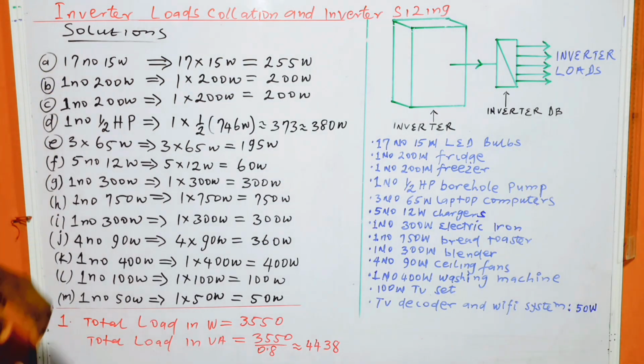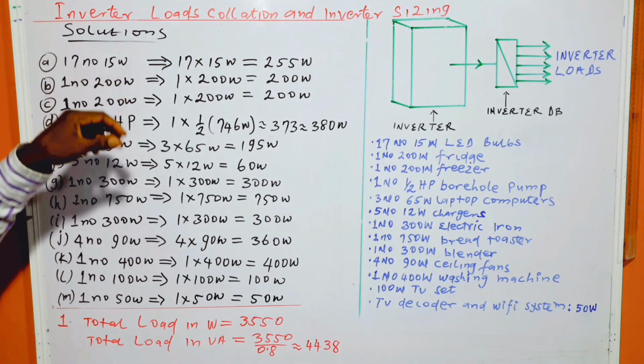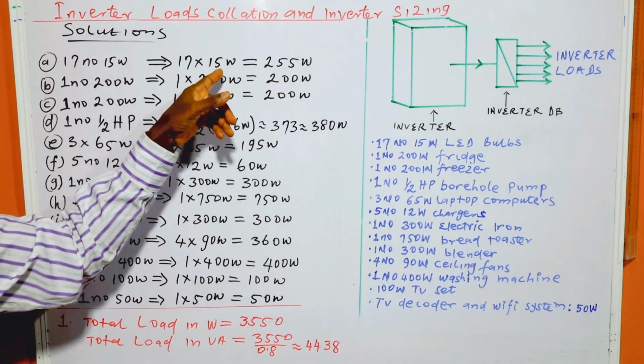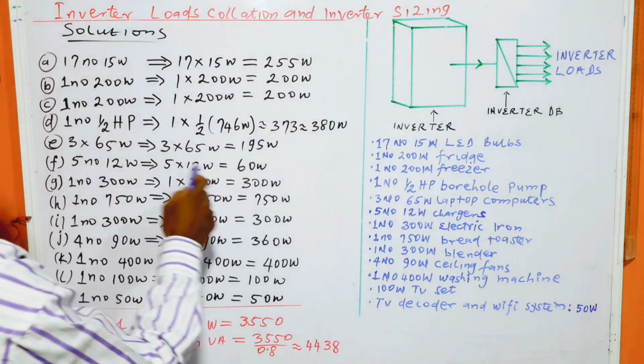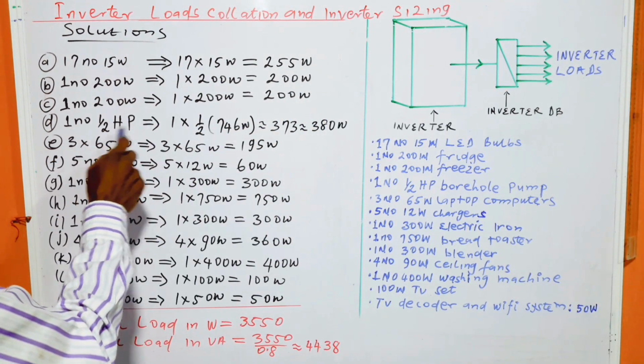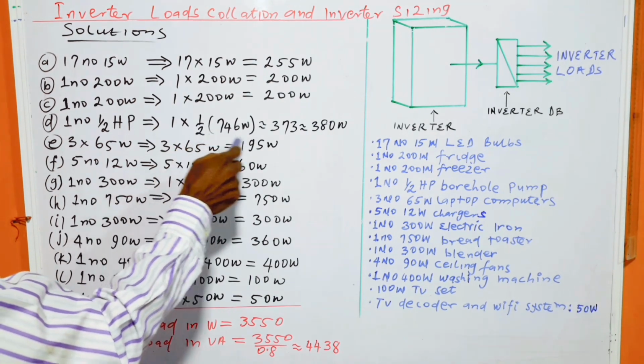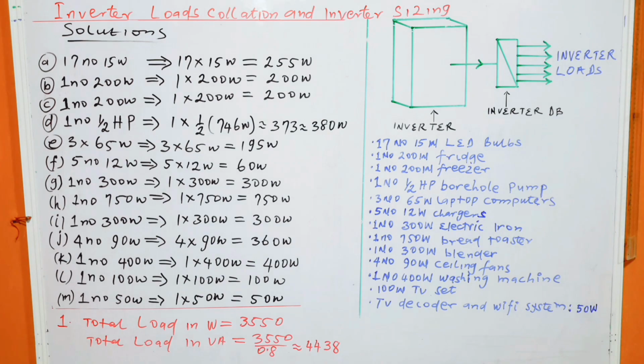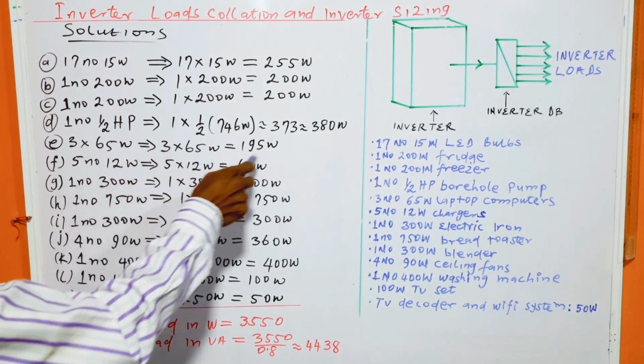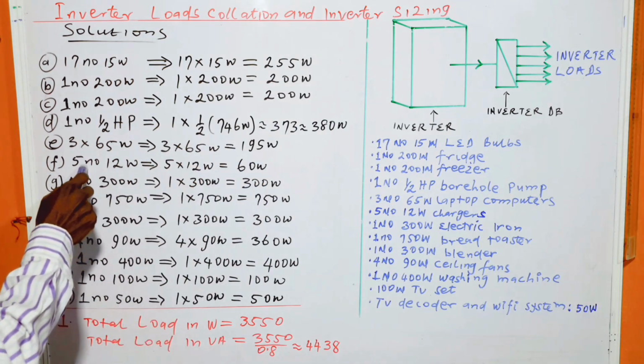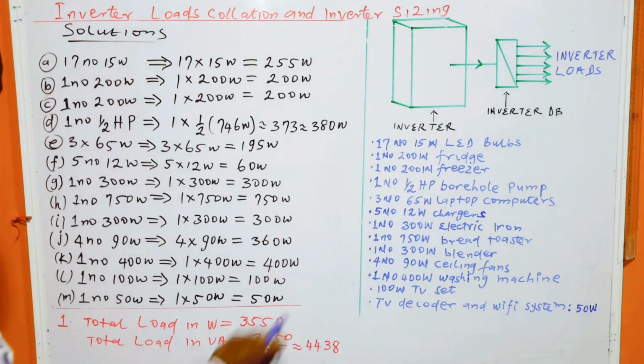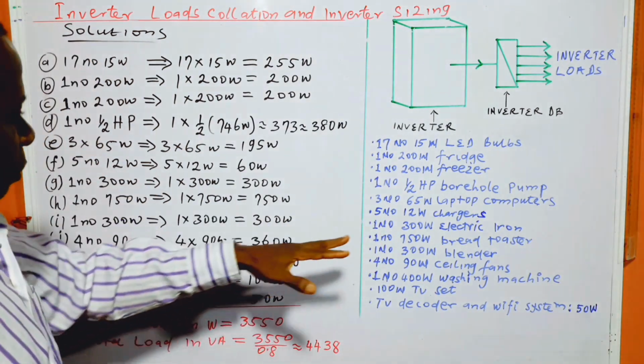We have 17 number LED bulbs, each rated 15 watts. If you multiply 17 by 15, it will give us this. Similarly, the fridge will give us 200 watts, and the freezer 200 watts. For the half horsepower borehole pump, 1 horsepower is 746 watts, so you divide 746 by 2, and it will give us approximately 380 watts. Then the laptop computers, 3 of them, will give us 195. The chargers, 5 of them, will give us 60 watts. The electric iron will give us 300 watts.